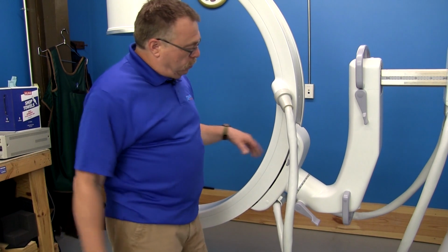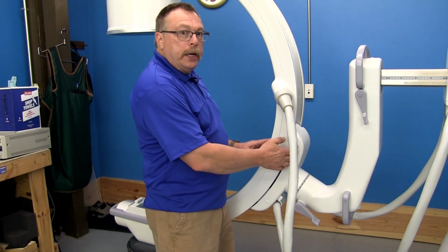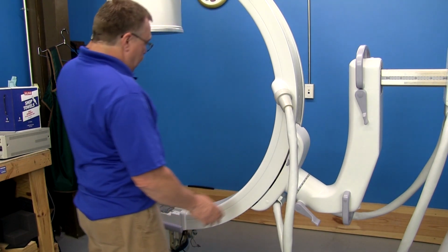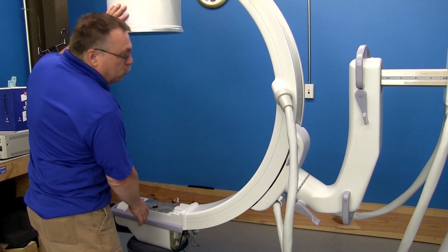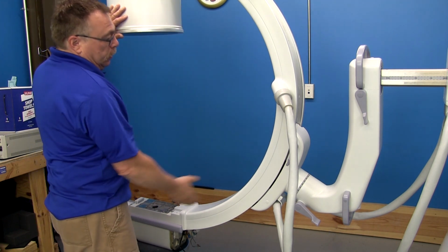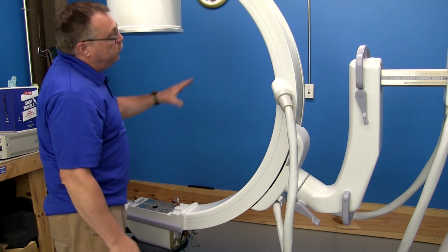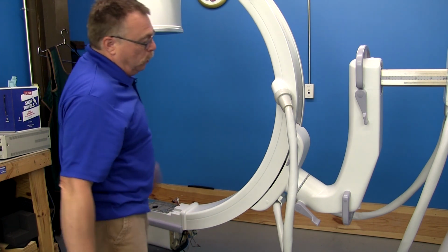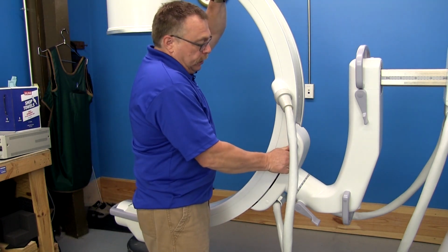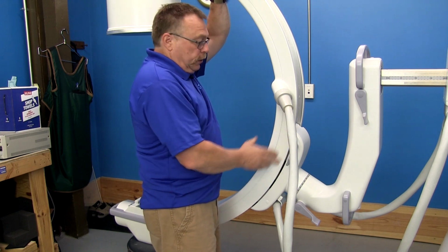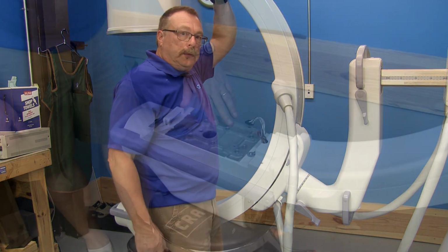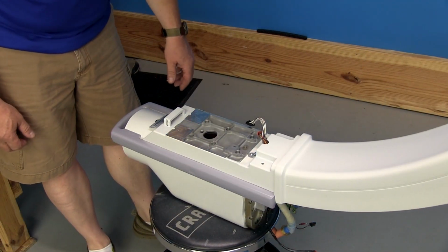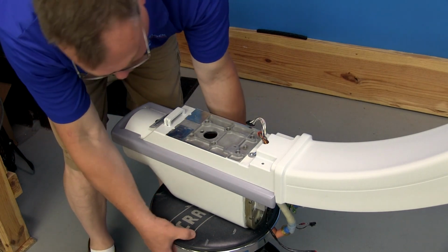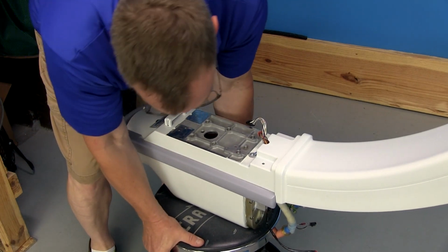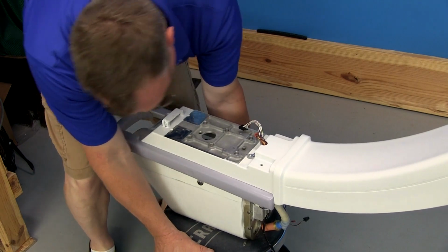At this point we should mention your orbital brake. The II and the tube, when they're on here, are center balanced. If you remove the tube, the II tends to want to roll. You want to make sure you've got this brake on and working well so it doesn't move once you take the tube off. Okay, we have the last four bolts out. Now all I do is grab my stool and push it down and the tube comes off.